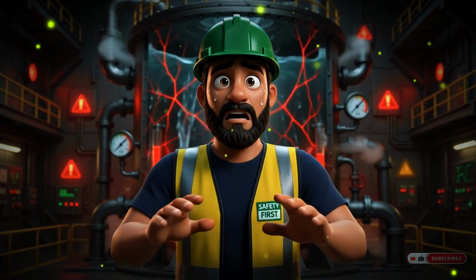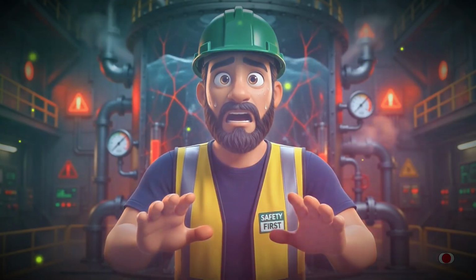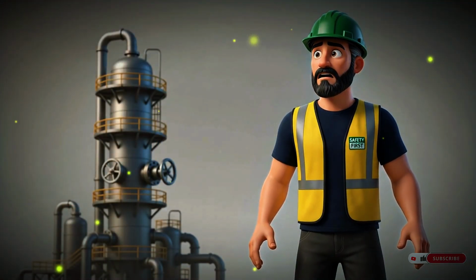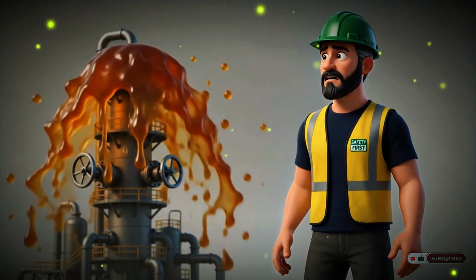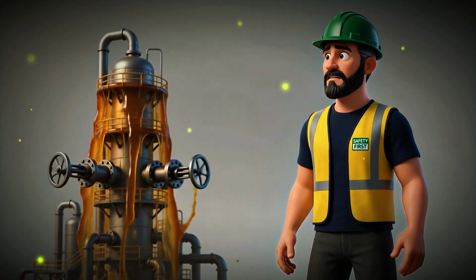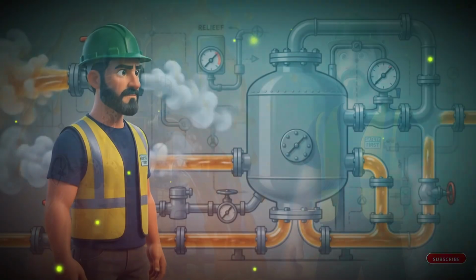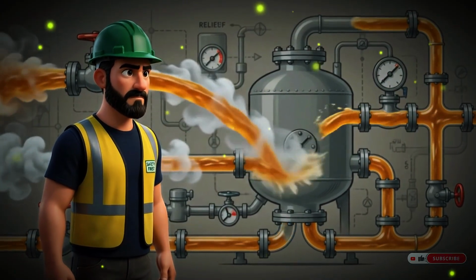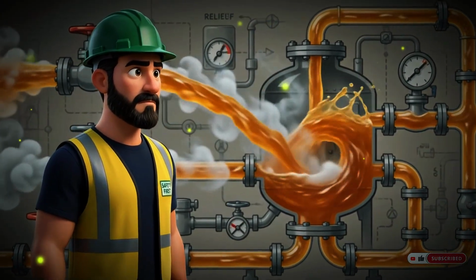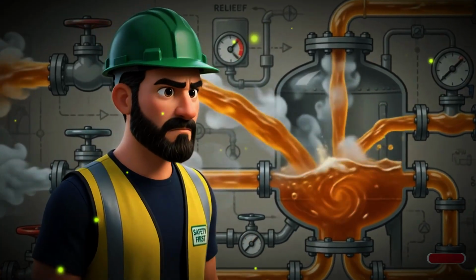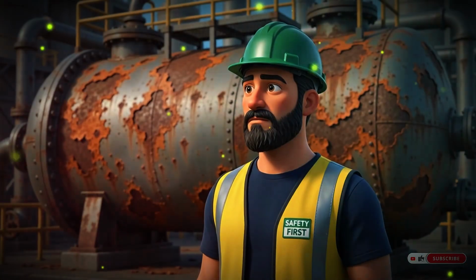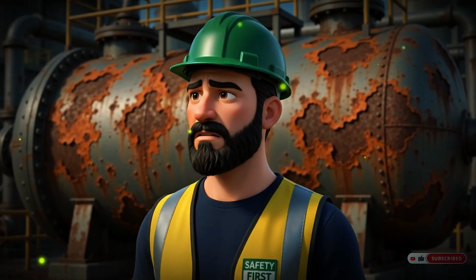With the tower completely filled with liquid under high pressure and temperature, liquid began to be forced out through the top of the tower, overwhelming the pressure relief valves. Those valves opened, exactly as they were designed to do, and began discharging liquid and vaporized hydrocarbons into the blowdown drum, that pressure vessel designed to receive and contain those emergency discharges.